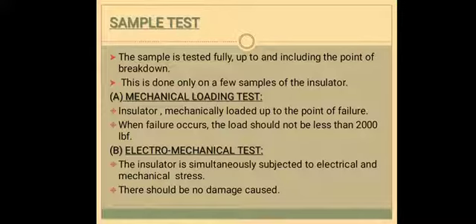Next is the electromechanical test. This test will be carried out only on suspension or tension type of insulators. The insulator will be subjected to two and a half times the specified maximum working tension maintained for one minute, and simultaneously 75 percent of the dry flashover voltage will be applied. The insulator should withstand this test without any damage.